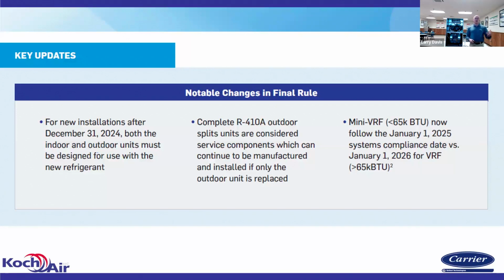You can replace components in a 410A split system or parts in a 410A package system. But if you replace the whole system, that has to be of the new refrigerant. Okay. And again, any questions on this, go ahead and put them in the Q&A box and we'll answer them as we go. The ductless system, that follows the same schedule as the split systems do. So January 1st, they have to be the new 454B or the new refrigerant, low global warming potential.